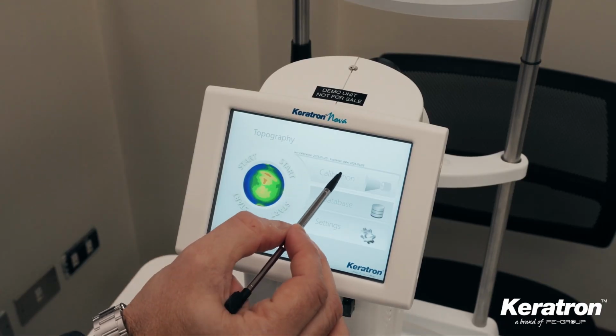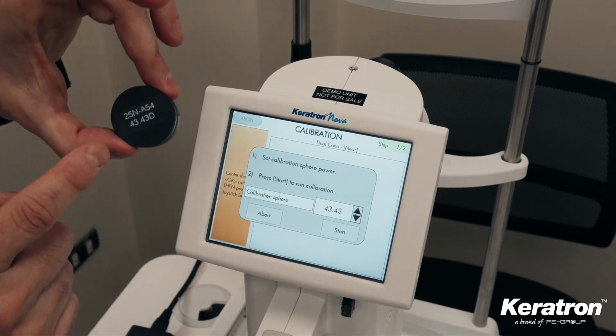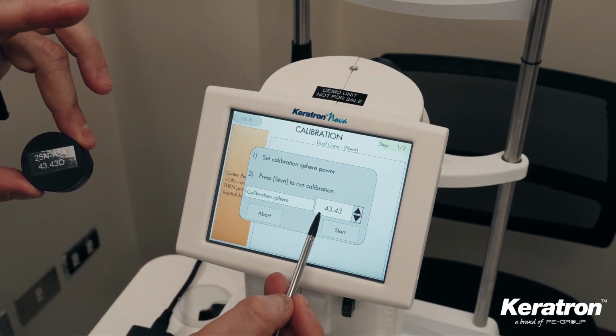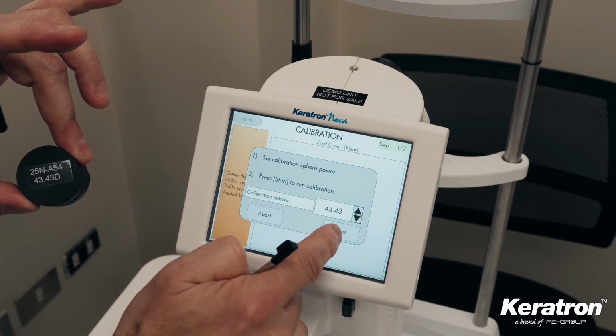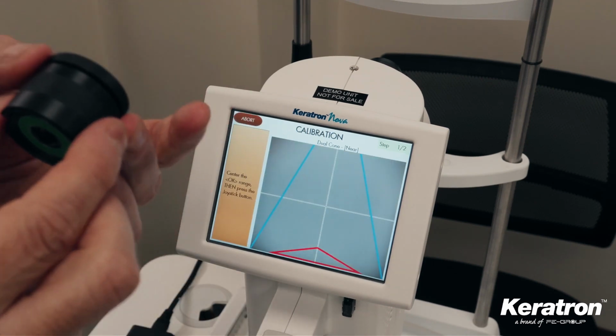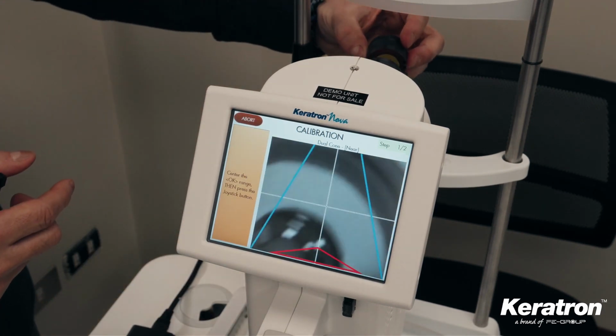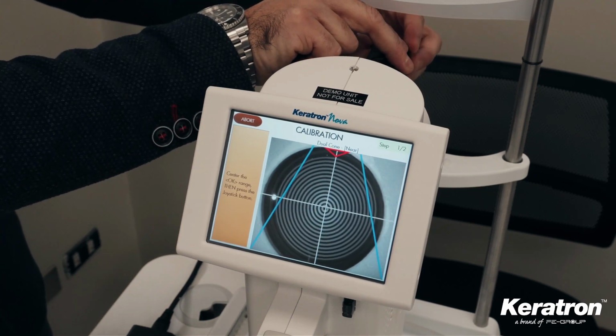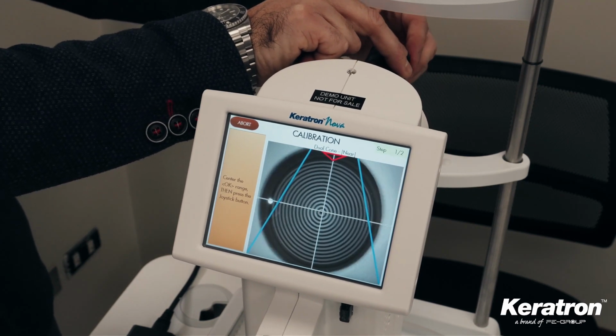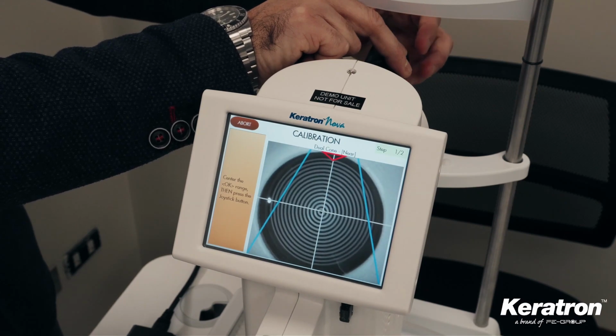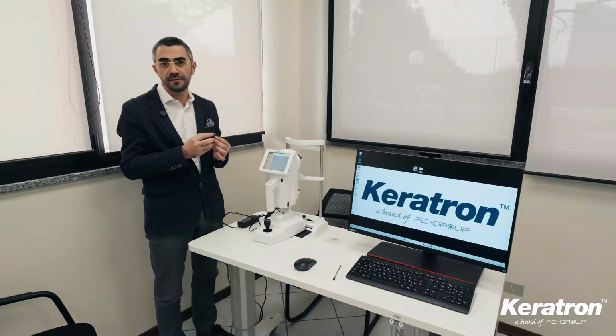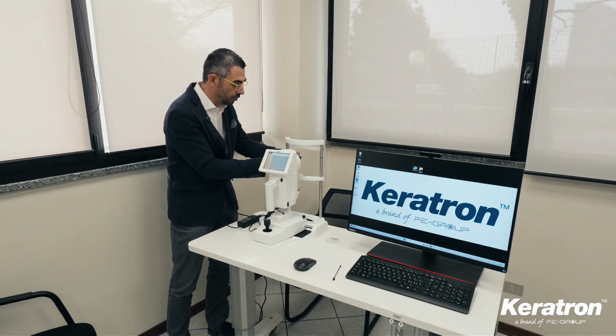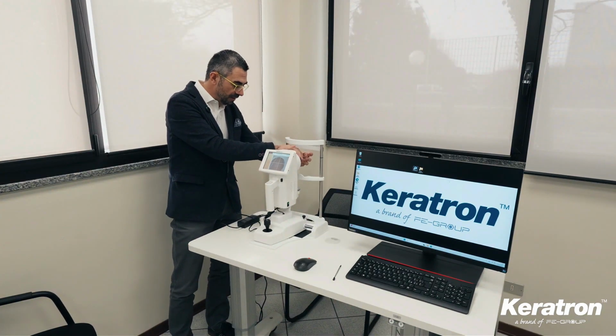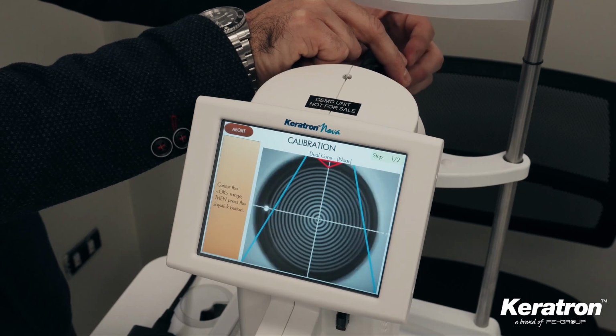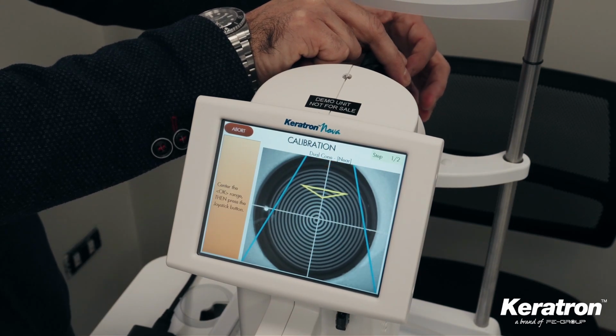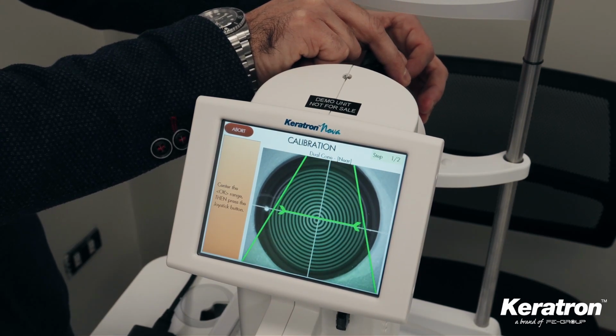How is it done? You click on the calibration button on the device, check that the diopter value on the test eye matches the one entered into the device, press the acquisition button, and then position the test eye in front of the cone. The test eye has a rotating ring which allows you to simulate movement. The forward and backward movement of the device will remain stationary in this case, unlike during a normal acquisition of an eye.